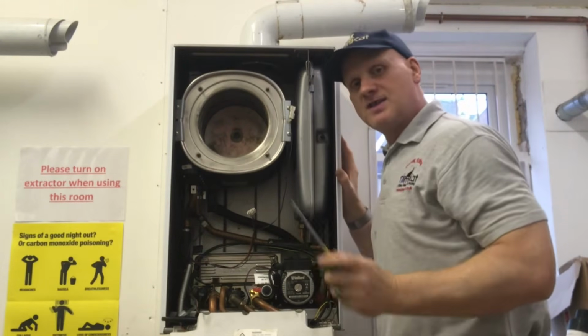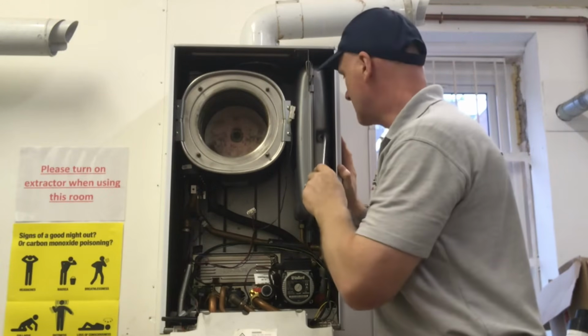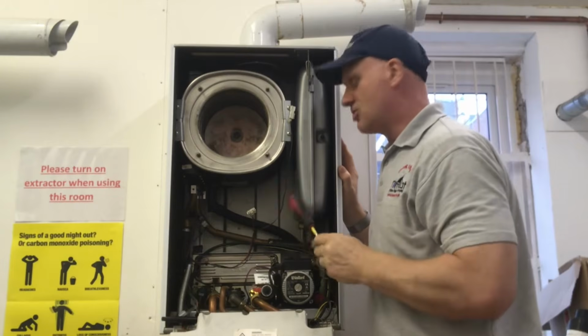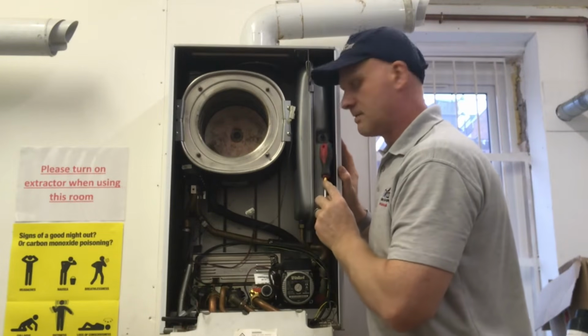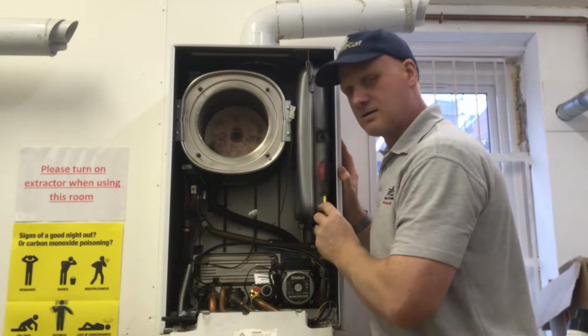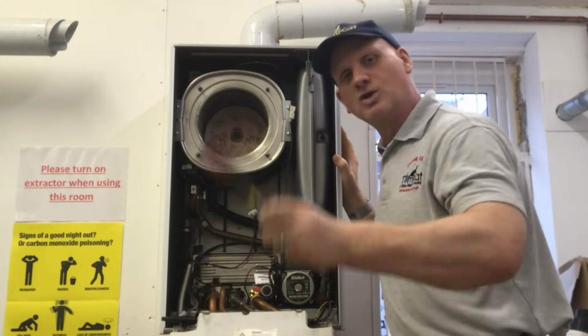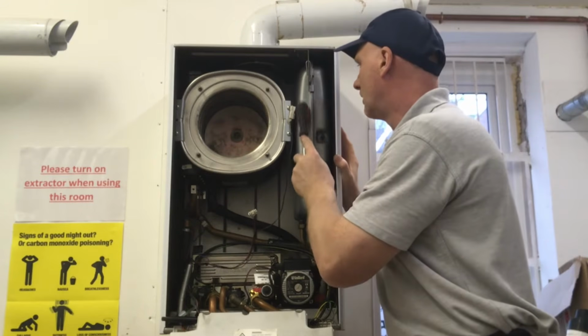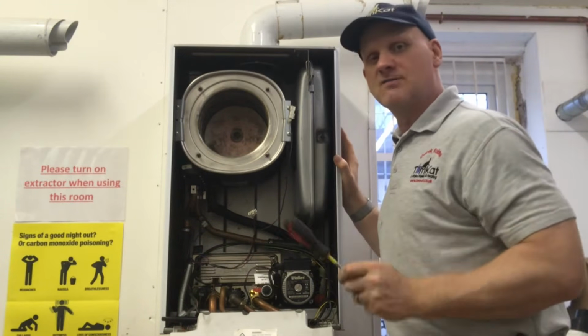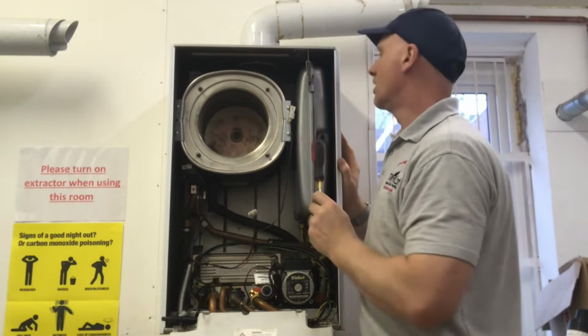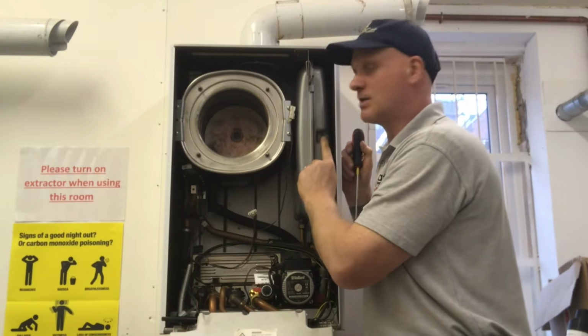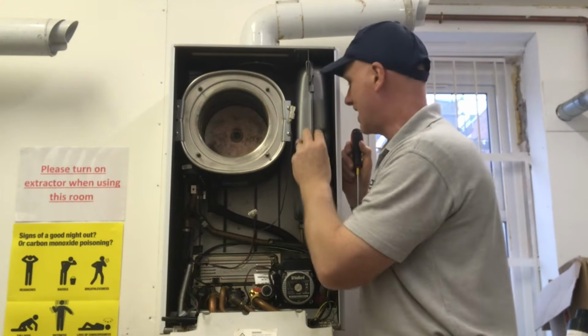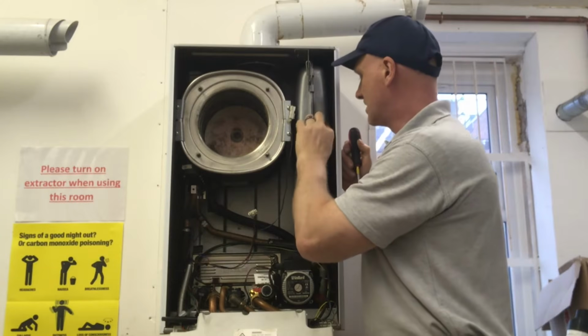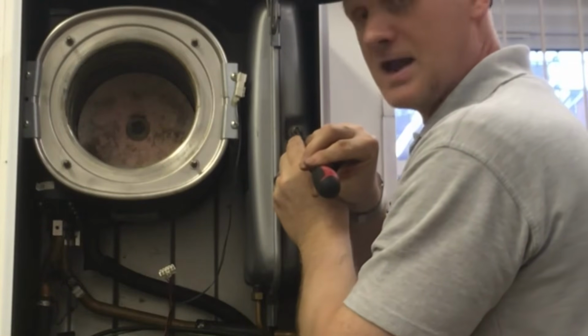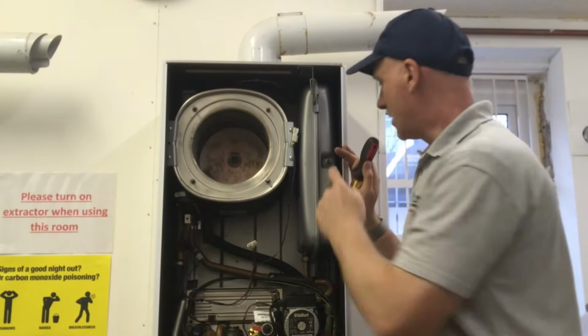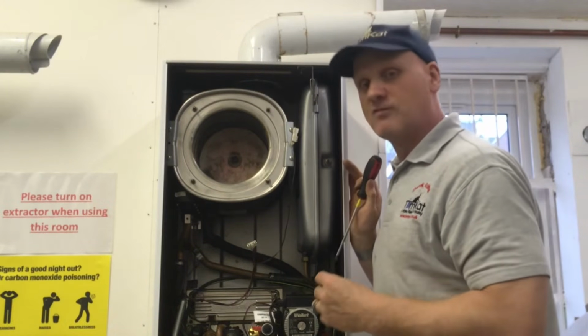Now, when you come to service these boilers, not every guy checks the pressure in these because it is a bit of a pain. Now, one of the things you can do is, if you tap one side, tap the other side, they should have different sounds because one's got water in, one's got air in. But if they both sound exactly the same, then you've got some problems. Now, if this does fill up with water, this Schrader valve here, which is the same as what is on your bike tyre or your car, again, if I press this in, and air comes out, then I know there's some air in there. But if I press that in and water comes out, then I know we've got a problem.